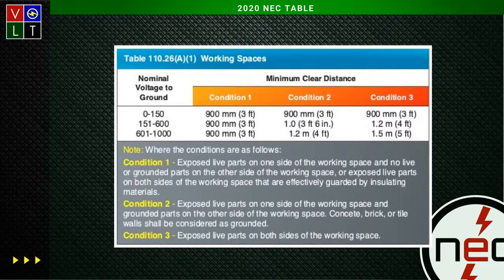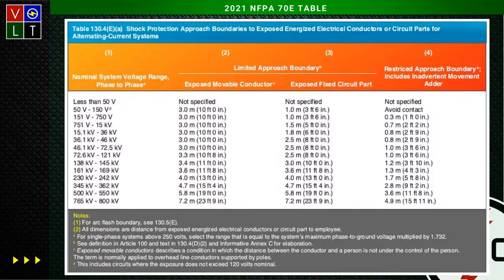Now I want everybody to see this. What'll happen next is right back where we were looking at 110.26(A), and I picked up informational note number 1. It said see 70E. Now I'm going to take the exact same thing here. We're working on an exposed fixed circuit part, 277 volts. If I look at my limited approach boundary, what does it tell me I need to be? 3.5 feet.